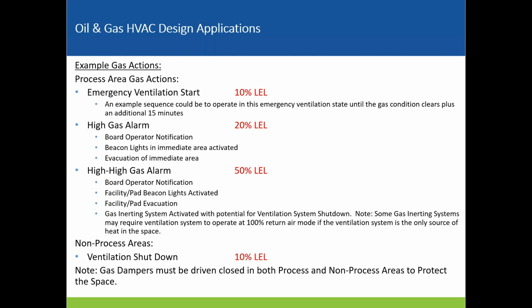One thing to note is with some gas inerting systems, they require the space to still be warm when they actually release. And it's just something we've been working through recently on our end. So otherwise it's going to be a puddle on the floor. So like Halon, Novec, you mean? Halon's okay. It's really the Novec 1230. Ideally you'd have the room be about 70 degrees when you release, because it's going to drop the temperature in that module immediately.